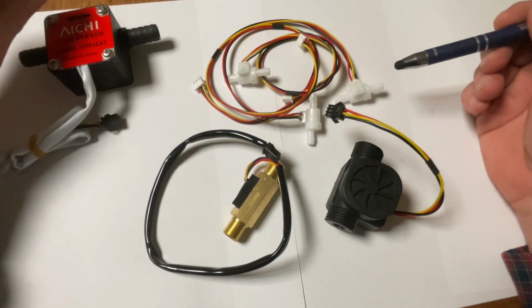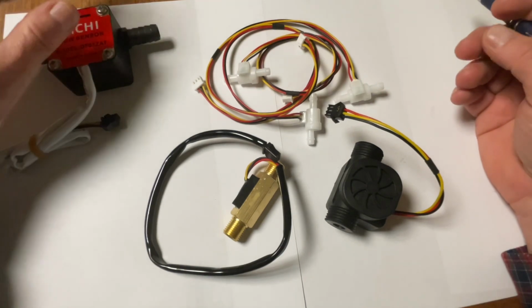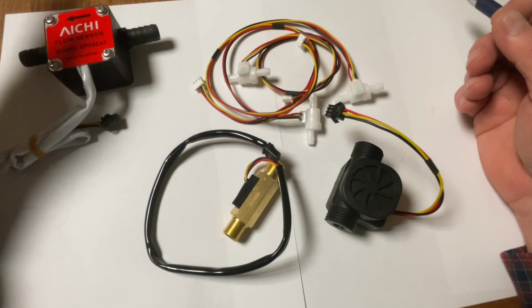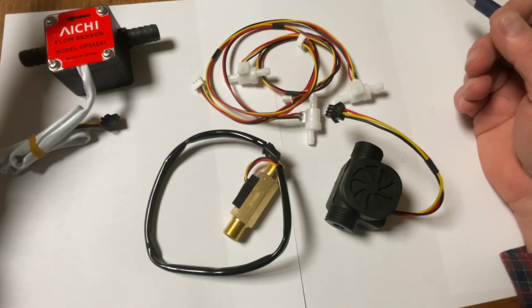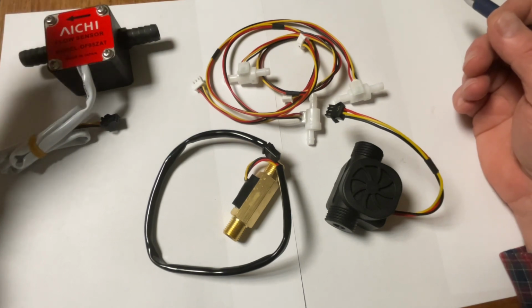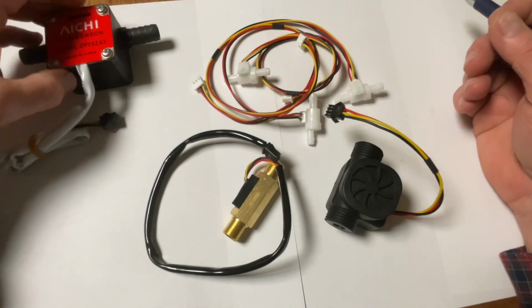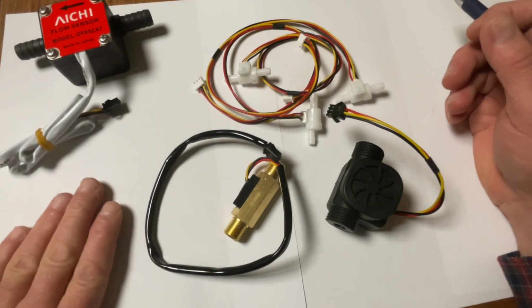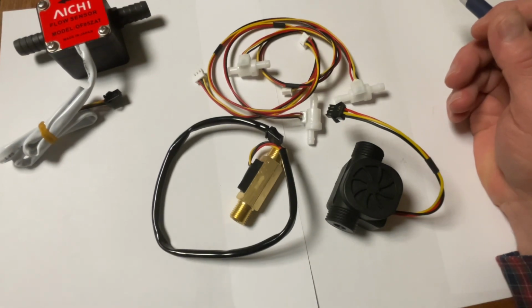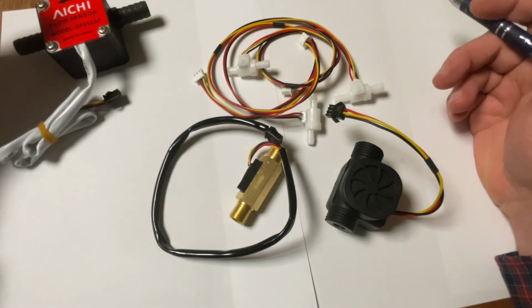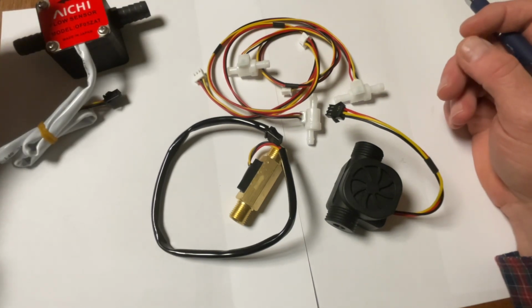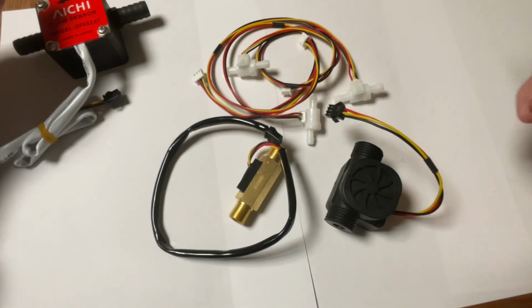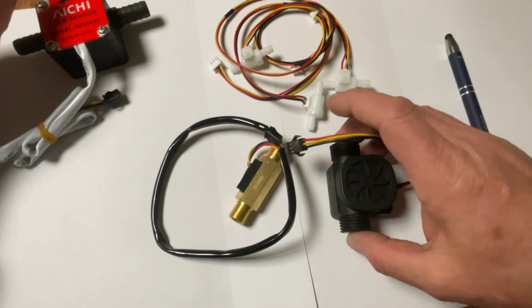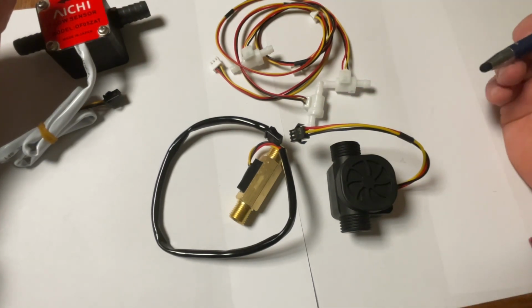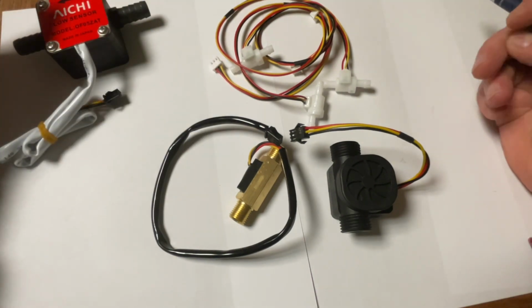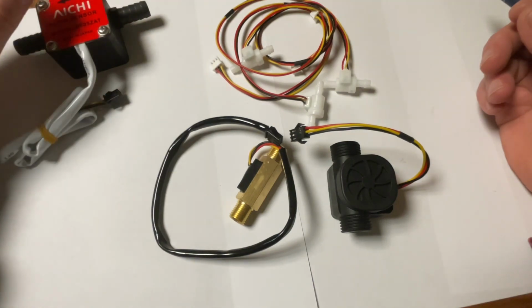The flow rates, we're looking at 4 milliliters per minute, 6 milliliters per minute at idle speed. With the resolution of these sensors, they should be 0.1 milliliter or 0.01 milliliter. Medical grade, because that's where you usually do the scientific medical. And the real high quality ones made in the United States, Japan, or in Germany, Switzerland, Austria, start at about $2,000 a piece and go to over $12,000. That is one thing which has not changed. Aalborg, the company which makes the water meter, also has digital flow sensors, but the resolution is too low for what we're looking at.